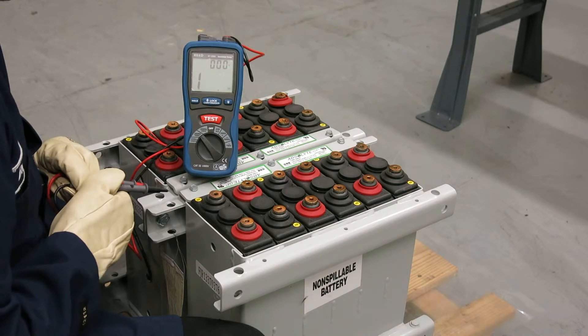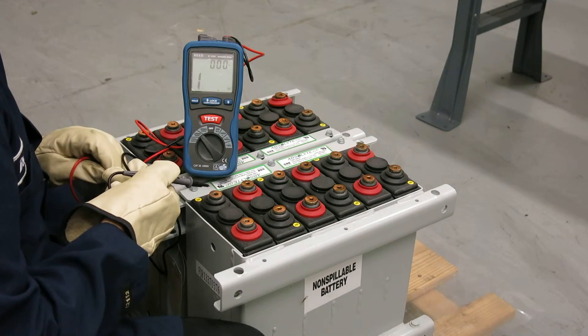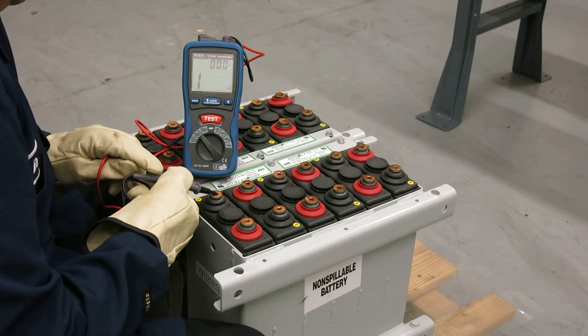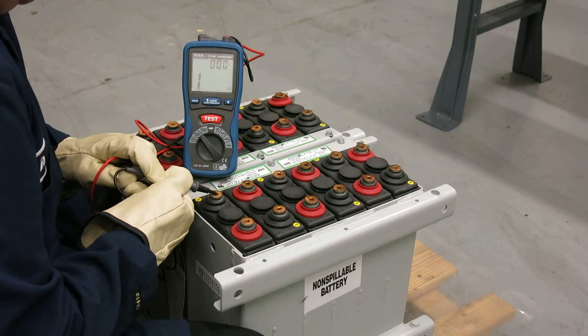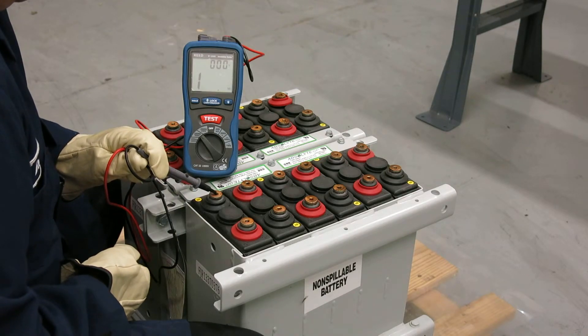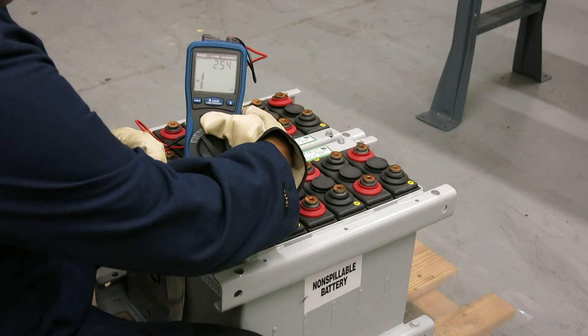The way this measurement is made is with an insulation resistance tester, commonly called a megger. One of the test leads is placed on the post of a cell. The second test lead is placed on a screw so that it is a grounded source, and we then push the test button.